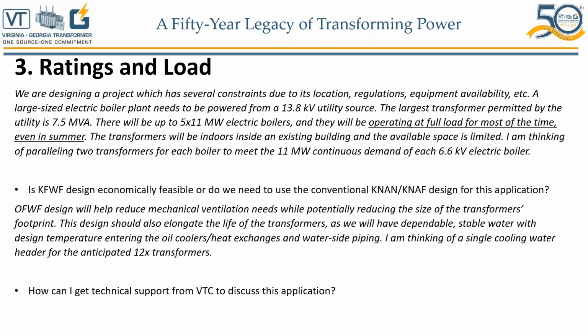OFWF design will help reduce mechanical ventilation needs while potentially reducing the size. So let me quickly explain OFWF. In this case, the first letter O stands for insulating liquid with fire point less than 300 degrees, okay? And the rest of them, FWF, is still the same as the forced circulation, water pumped, and of course the forced circulation of the fans and everything else. So with that said, it continues.